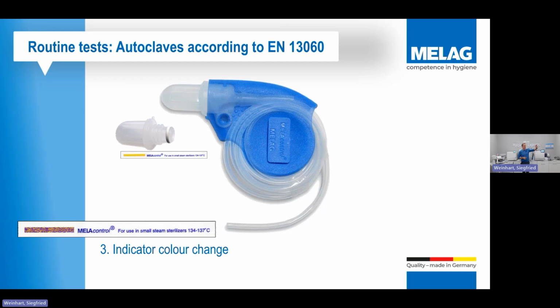What happens then is that indicator will change color. And by that indicator changing color, it shows you that a vacuum has been pulled and that steam has been able to penetrate the entire 1.5 meters and get to that little test strip. So it's showing you that if you put a handpiece through there, that handpiece will get sterilized correctly right the way through the chamber, because there's no handpiece that has 1.5 meters worth of tubing, internal lumen. I mean, that would be a whopping great big handpiece if there was. So no.